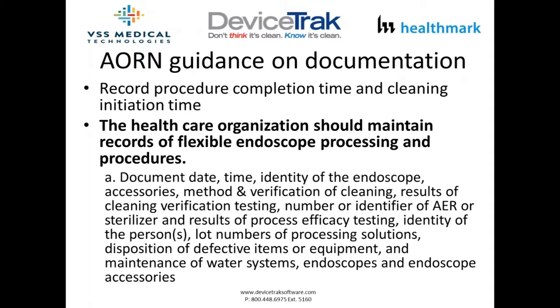AORN states you need to record the time the procedure is completed and the time manual cleaning is initiated. This matters because some endoscope manufacturers have a one-hour hold time — a one-hour delay allowed between when the procedure ends and when manual cleaning starts. By documenting procedure completion time and cleaning initiation time, you know whether you've exceeded that one-hour hold time. This delayed reprocessing guidance is written into the AORN documentation requirements.